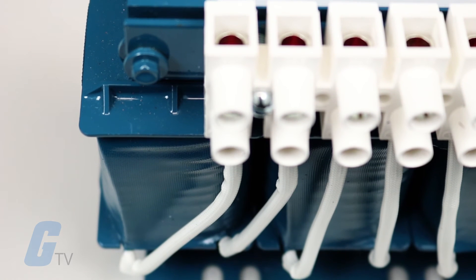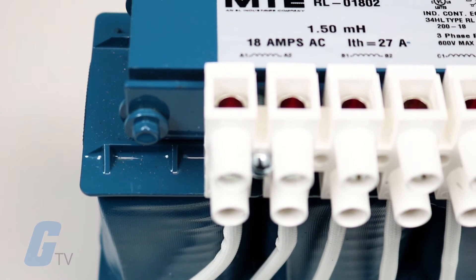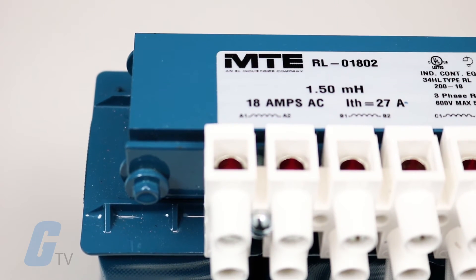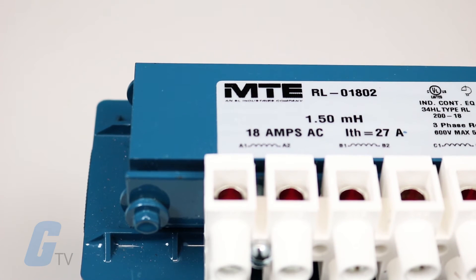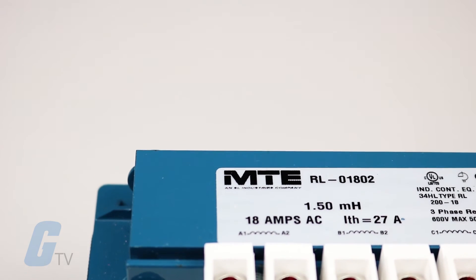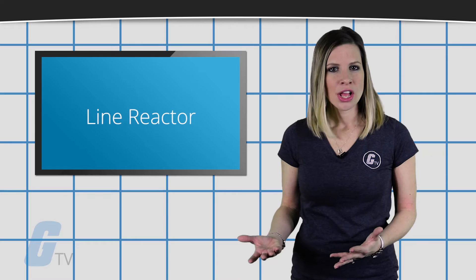You can often safely pull 200% of the rated amps for up to 10 seconds per hour or 150% for up to 1 minute per hour without damaging the reactor.